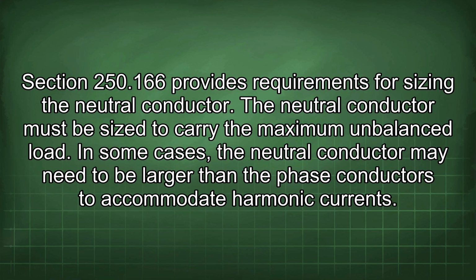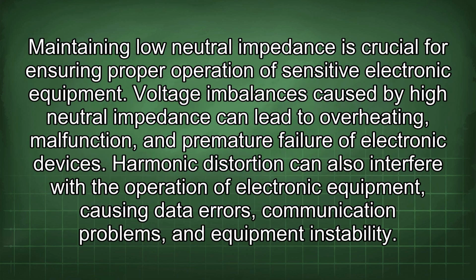The neutral conductor must be sized to carry the maximum unbalanced load. In some cases, the neutral conductor may need to be larger than the phase conductors to accommodate harmonic currents. Maintaining low neutral impedance is crucial for ensuring proper operation of sensitive electronic equipment. Voltage imbalances caused by high neutral impedance can lead to overheating, malfunction, and premature failure of electronic devices.